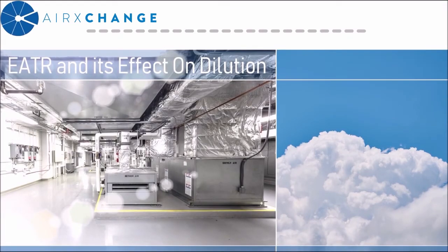As a rule of thumb, we advise against using plates and wheels in Class 4 air streams. The ventilation standard included air classifications and energy recovery guidance to take the guesswork out of acceptable levels of transfer and provide proper guidance on balancing systems. However, we are a conservative industry, and there is a perceived risk and potential for transfer, so I wanted to take a few moments to discuss the practical effects of the 5% and 10% requirements.